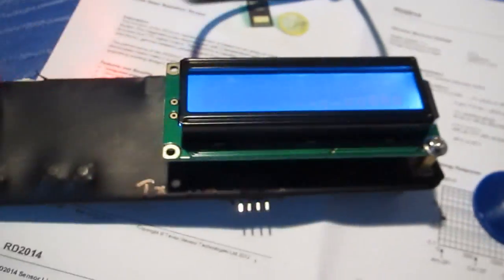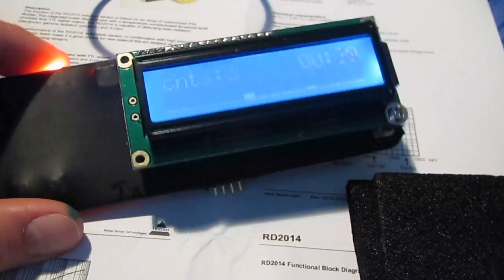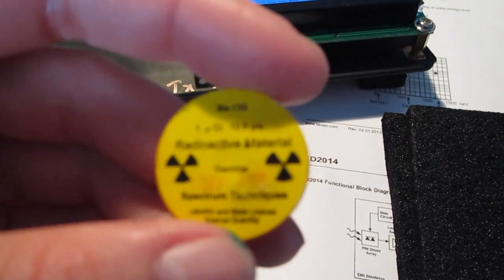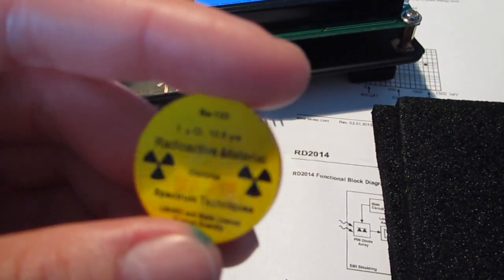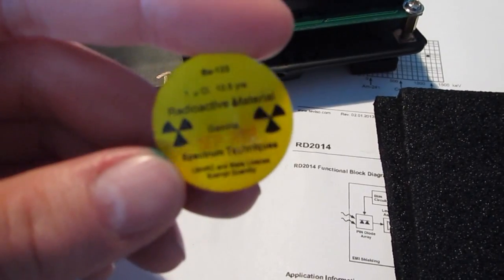So if we reset the device, after resetting the device we're going to use a Barium-133 calibration source, which has lower energy gamma radiation, something around 300 keV.